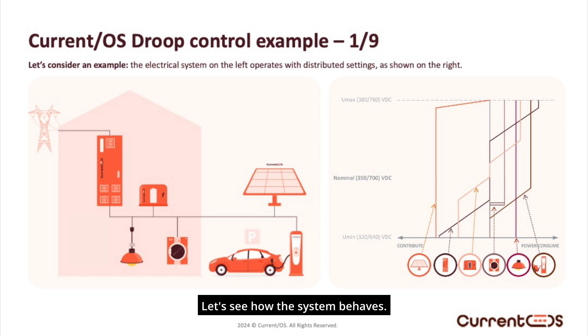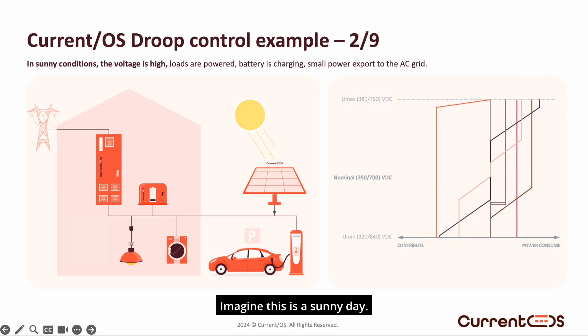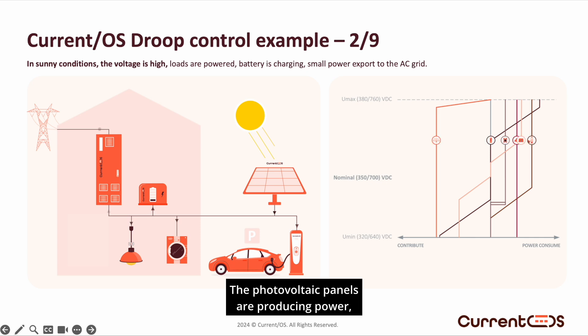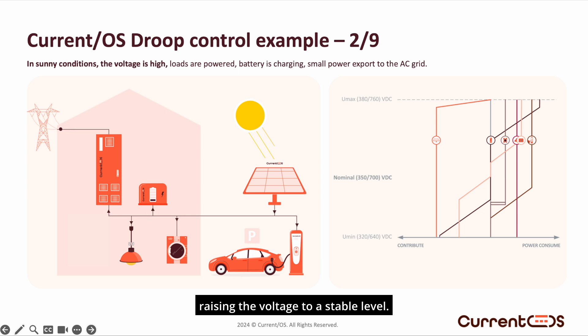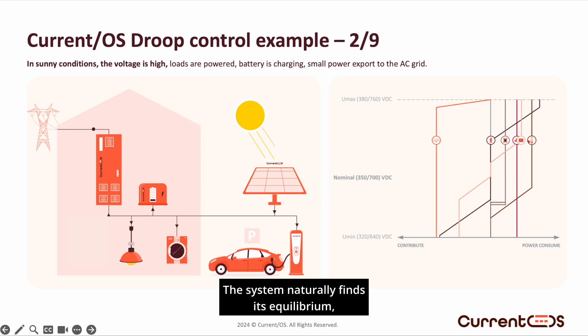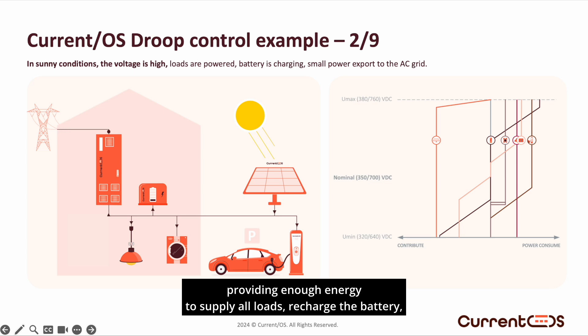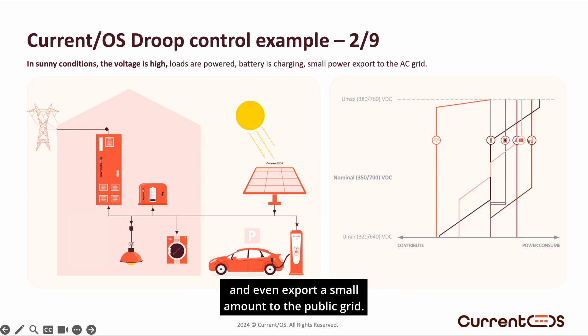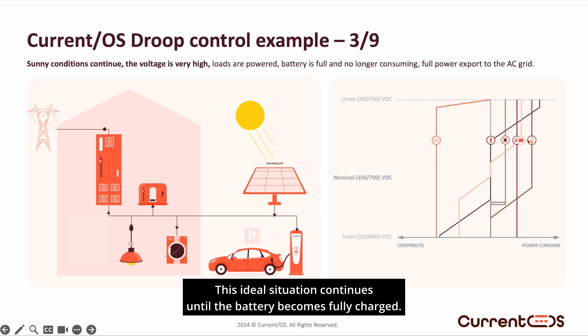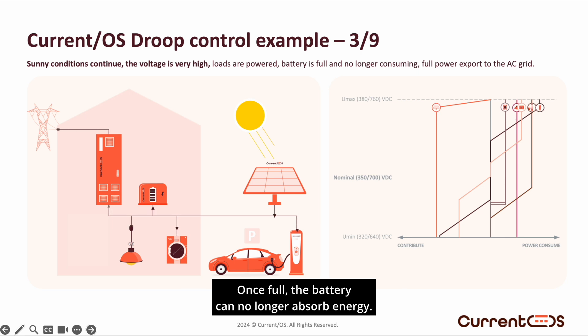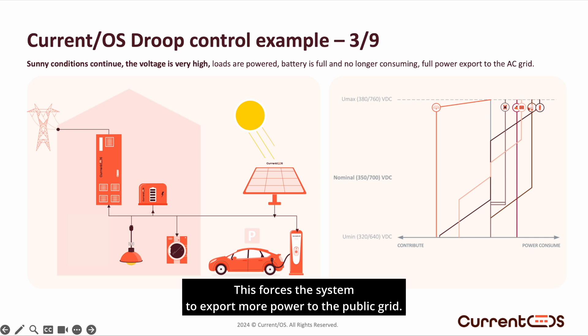Let's see how the system behaves. Imagine a sunny day: the photovoltaic panels are producing power, raising the voltage to a stable level. The system naturally finds its equilibrium, providing enough energy to supply all loads, recharge the battery, and even export a small amount to the public grid. This ideal situation continues until the battery becomes fully charged. Once full, the battery can no longer absorb energy. As a result, the system voltage rises to a higher level, finding a new equilibrium, and the system is forced to export more power to the public grid.